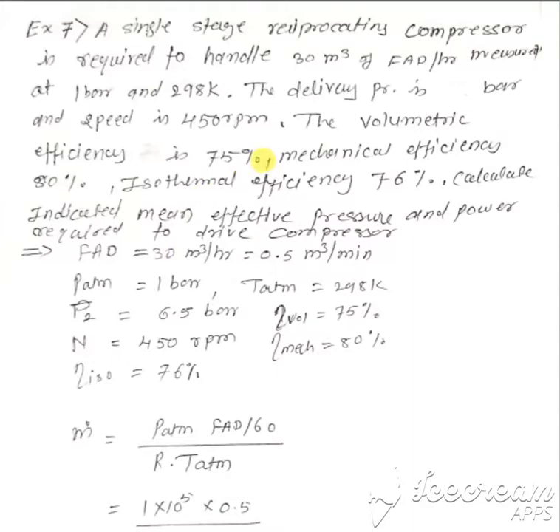FAD is given as 30 meter cube per hour. We have to write FAD in meter cube per minute, which is 0.5 meter cube per minute. With FAD, pressure and temperature are always atmospheric, therefore atmospheric pressure is 1 bar and atmospheric temperature is 298 Kelvin.